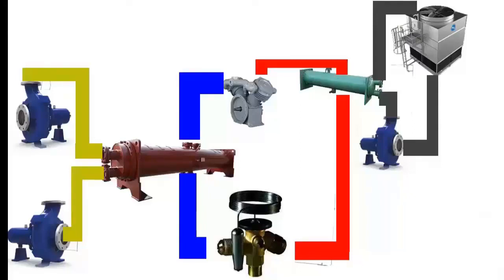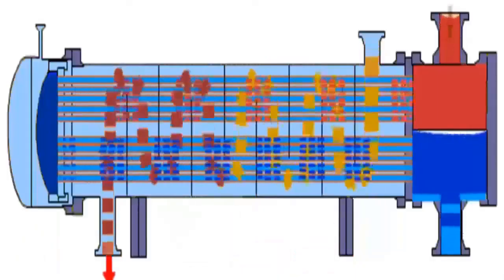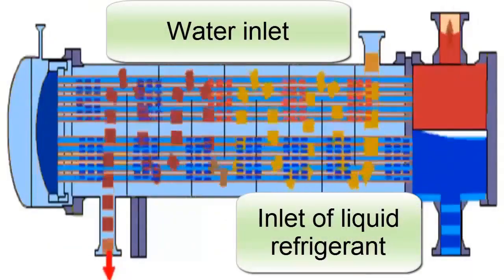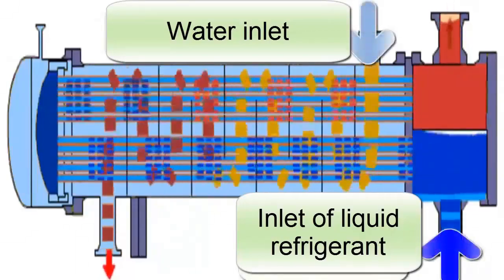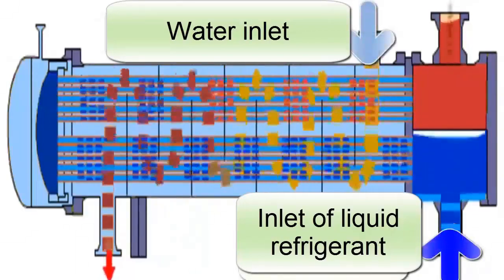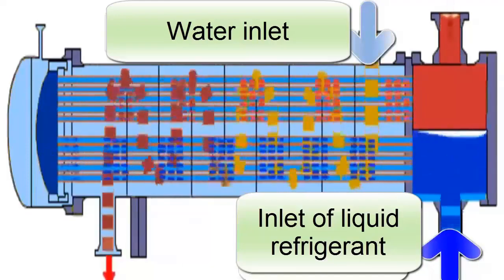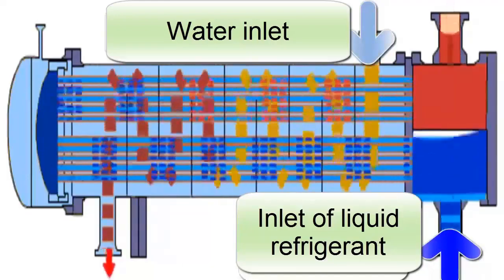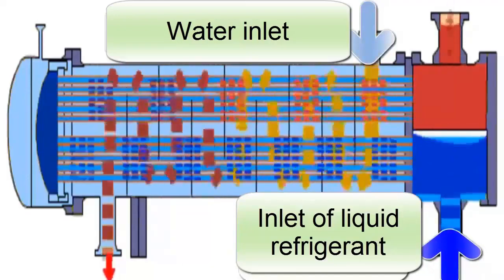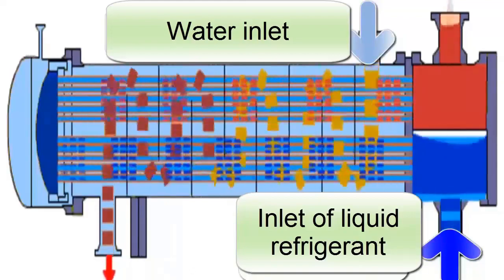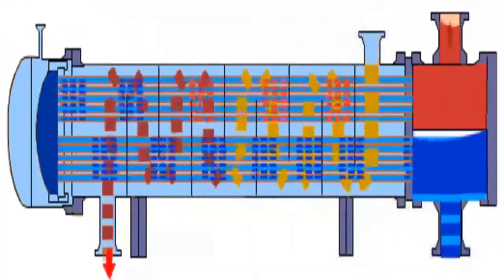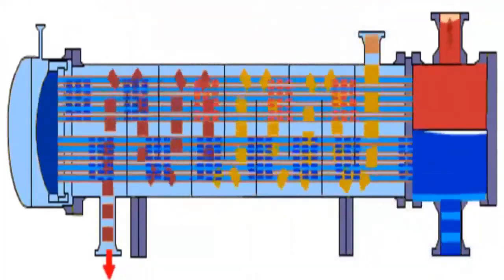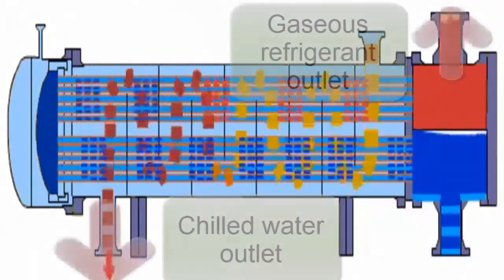The refrigerant is in the chiller evaporator and since it has a low temperature, due to the low pressure that the compressor causes by sucking the refrigerant, the pressure drops and when the pressure drops we have a low temperature. That low temperature allows the heat from the ice water to pass into the refrigeration circuit, causing the refrigerant to begin to evaporate.